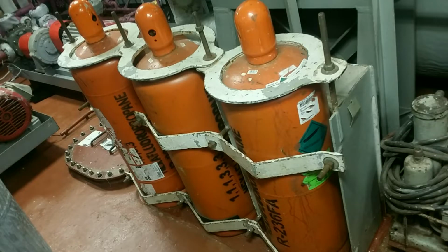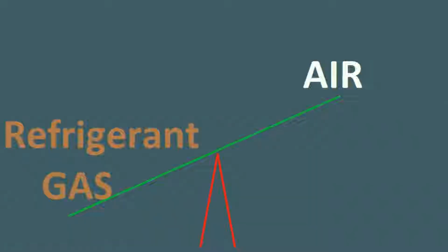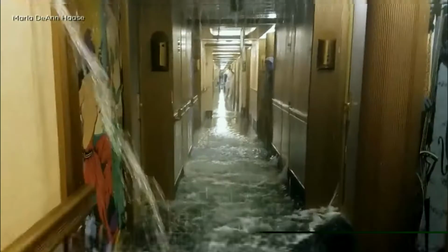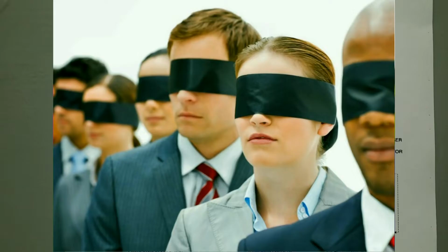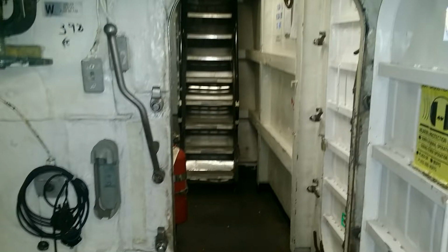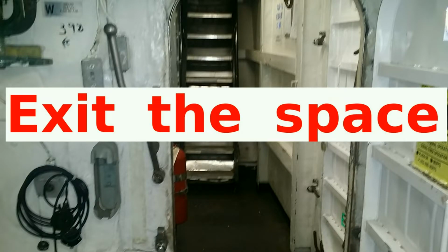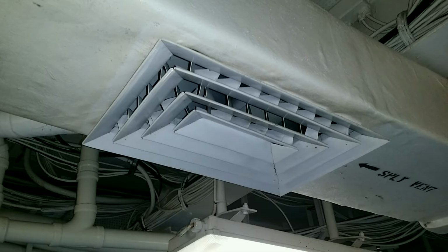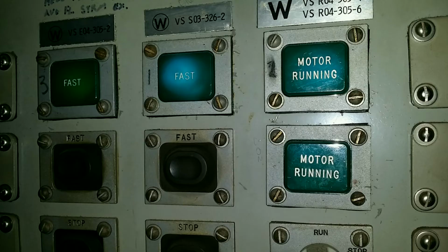Before we continue, let me remind you that the refrigerant inside this unit is heavier than air. If there is a leak, it will flood the space just like seawater floods the space. But the problem is you cannot see it and you start suffocating very fast. So if you have difficulty breathing, run, because you only got a few seconds of air. So it's very important that whenever you are working close to one of these units, ventilation is properly working.